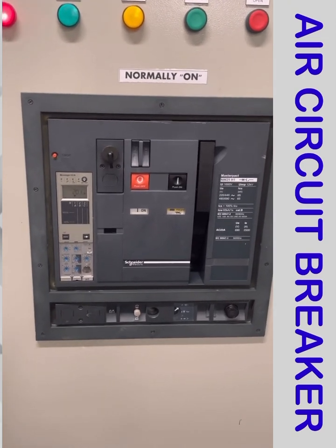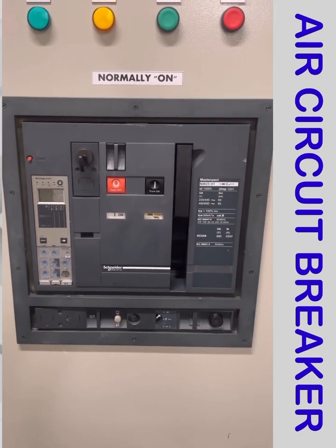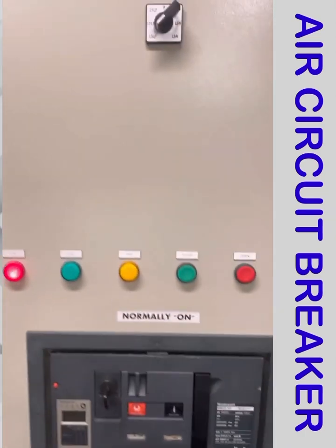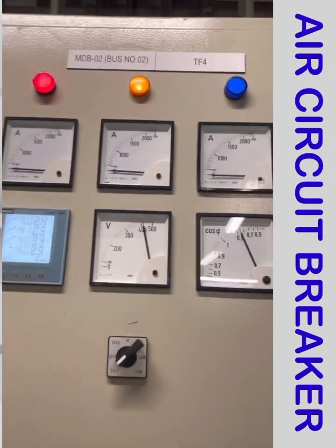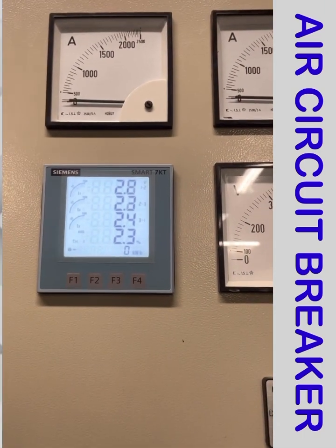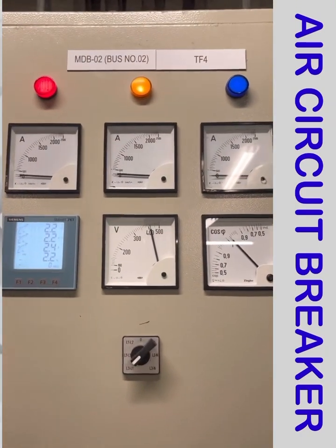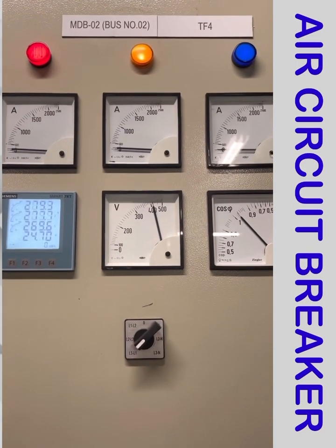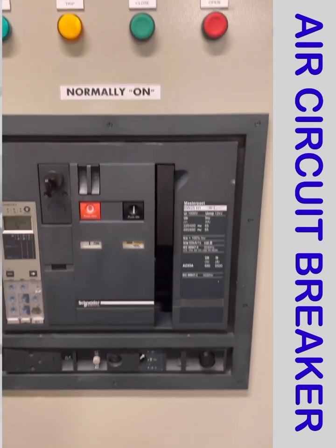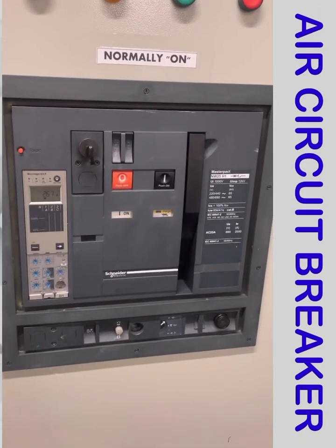Hello, I am in front of an air circuit breaker, also called an ACB. This is the main incoming breaker connected from the transformer. You can see the ammeter, voltmeter, and multifunction meter where you can check voltage, current, frequency, and energy. These are the indication lamps for R phase, Y phase, and B phase, so we can know the presence of each phase. Today our discussion is about how we can set and understand the long time, short time, instant, and ground fault current of the breaker.